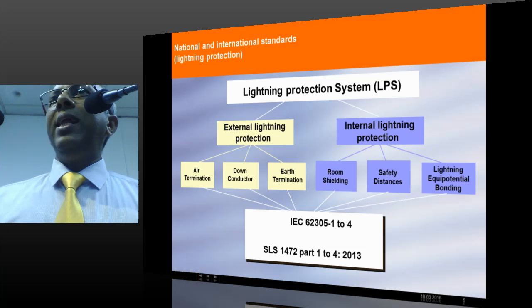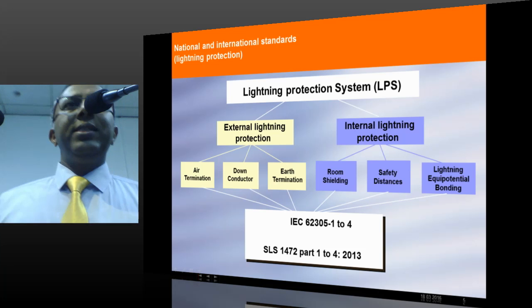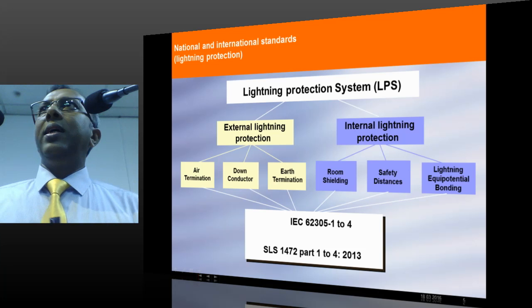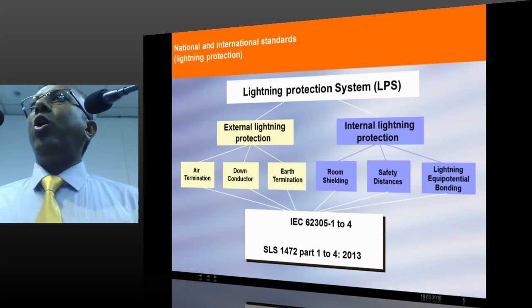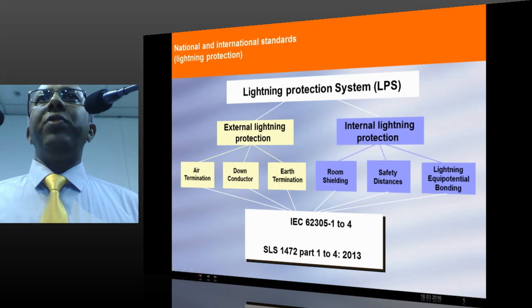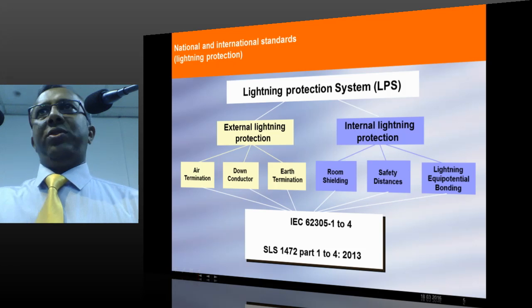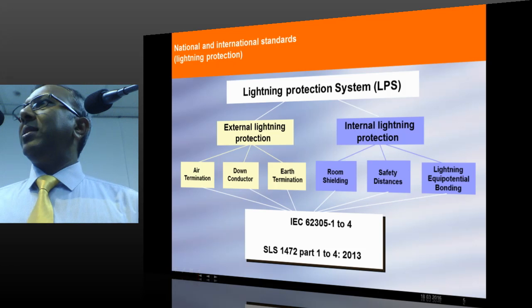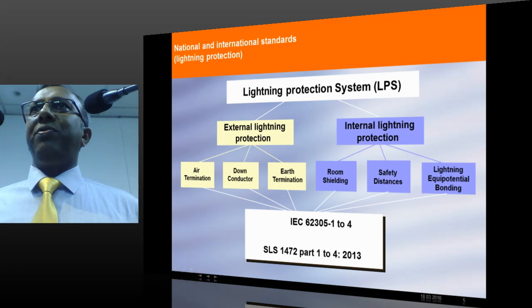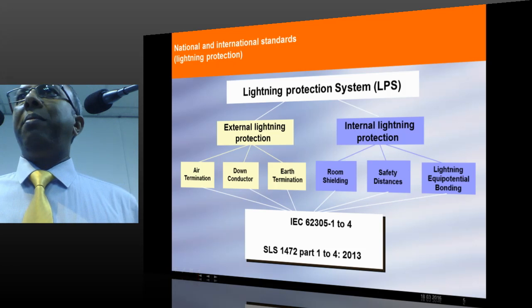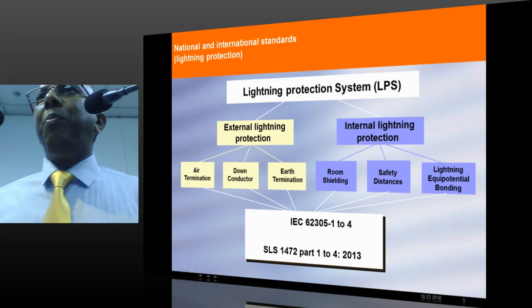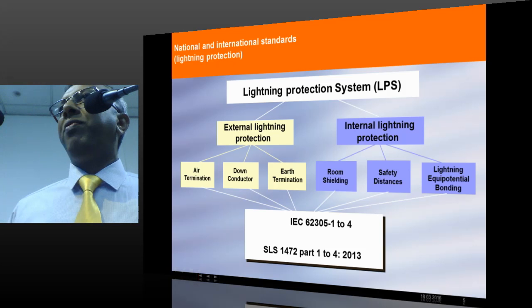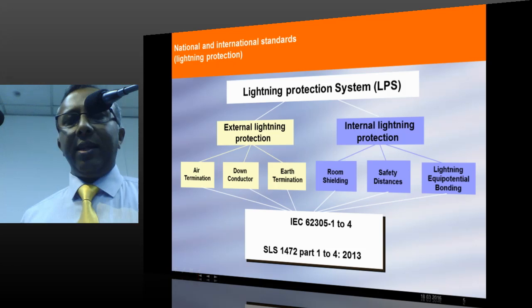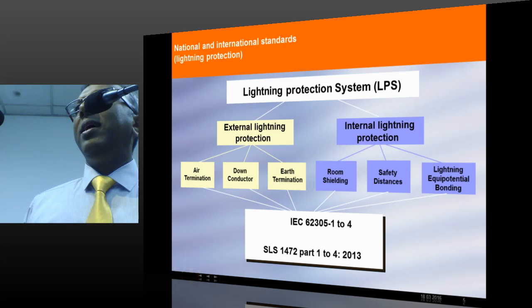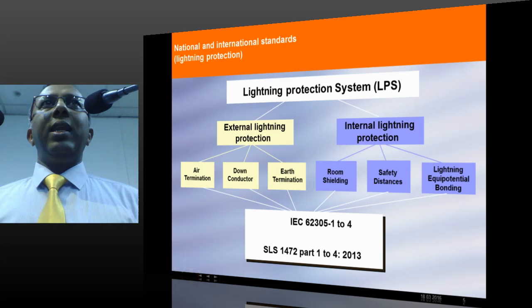Most of the buildings in our area, in the Asian countries, the down conductor designs are not proper. In several places we use a single down conductor, which is dangerous. Two down conductors, sometimes, which is to satisfy some of the standards, is also sometimes dangerous. So depending upon the size of the building, you need a certain number of down conductors, which we explain later. And similarly, the third point in external lightning protection is the earthing system.